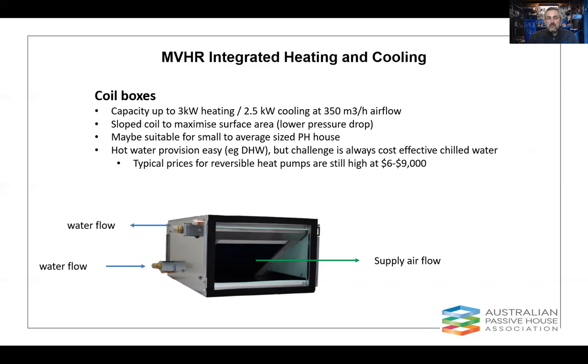You can see this one's got a sloped coil. What that does is allow the manufacturer to maximise the surface area, so we can get capacities up a little and we can get coil pressure drop down, which is important because you've got airflow running over that coil every day of the year, even when it's not in use, so it needs to be designed such that pressure drop's pretty low, i.e. you haven't got overhead fan power consumption that's horrendous.